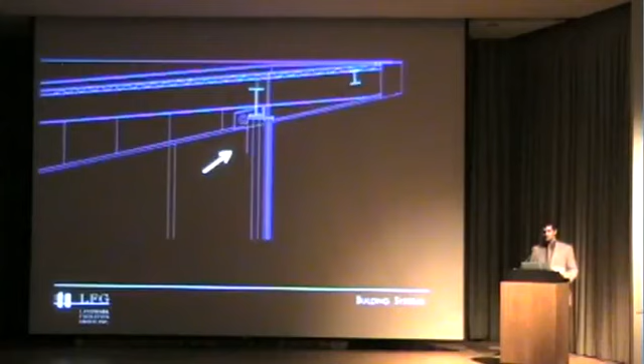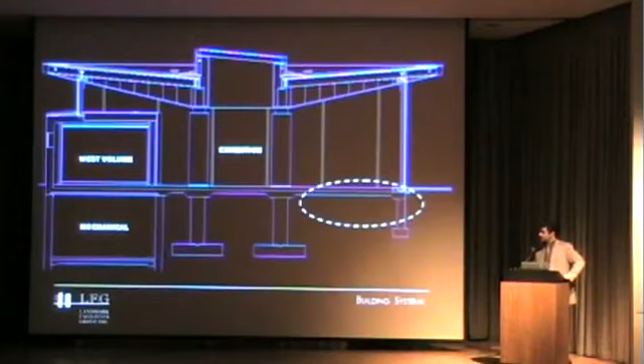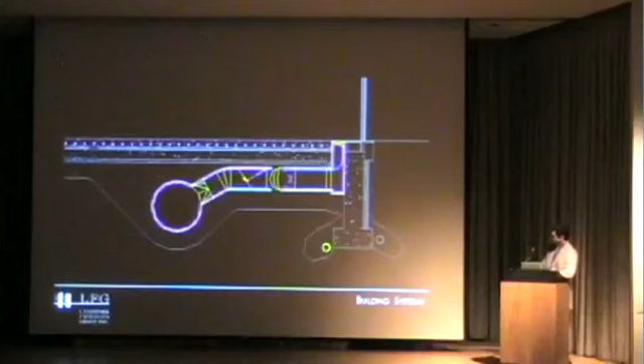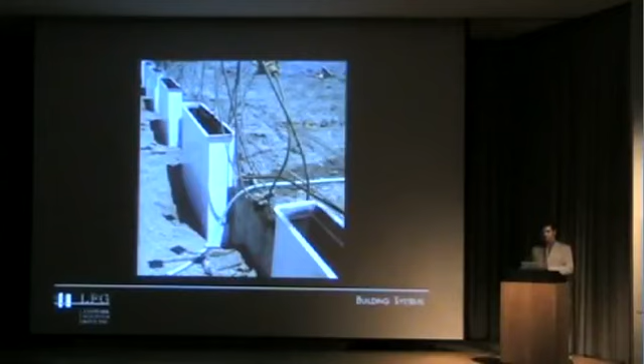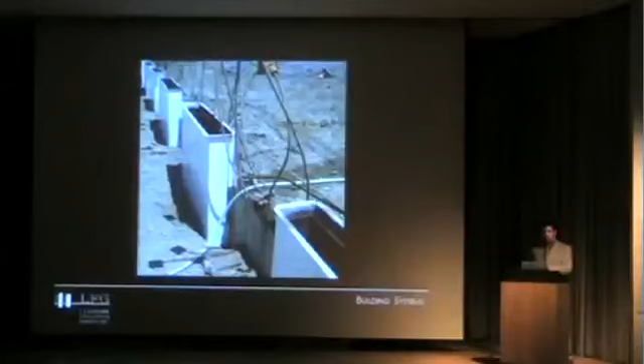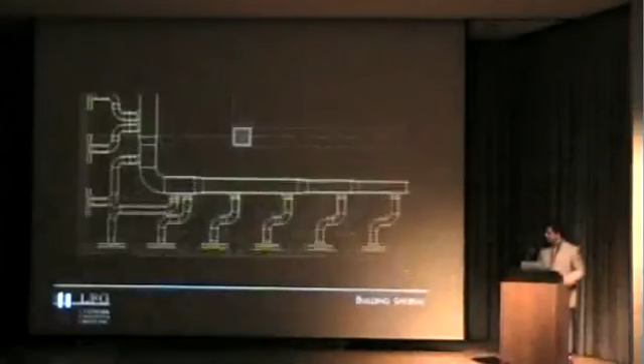In addition to dealing with these solar loads, we had a great deal of challenge with engineering acoustics. We focused our acoustic work and absorption on the ductwork below the floor slab. We started off by slowing the air down at all of the air outlets. The air outlets surround the perimeter of the building, and there are separate branch ducts. As you can see, each one is an oversized outlet, so the air moves very slowly through these under normal operating circumstances, and the low velocity helps us reduce that outlet noise that most people are so accustomed to with an air system.